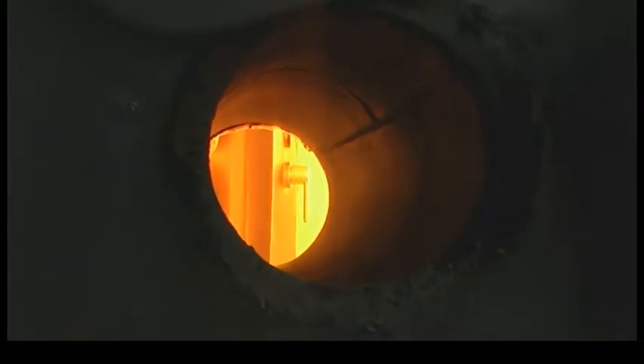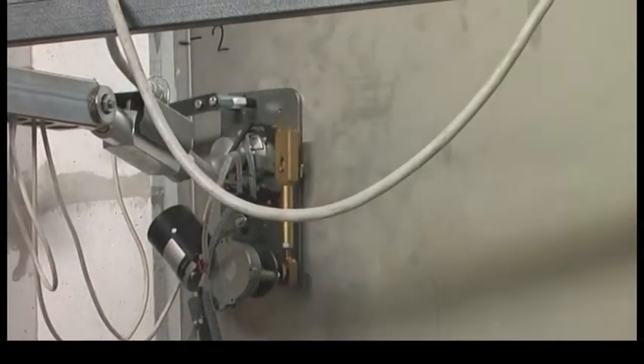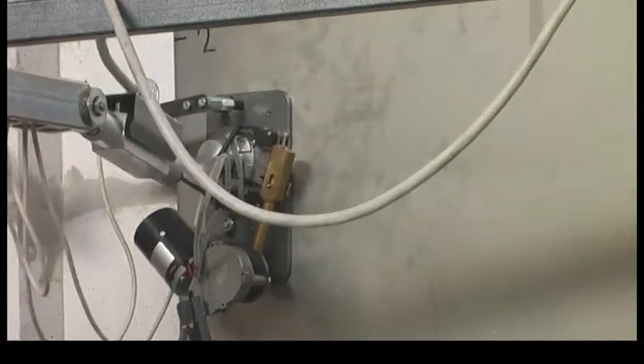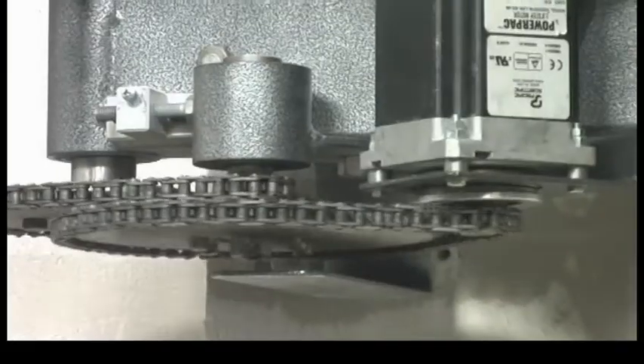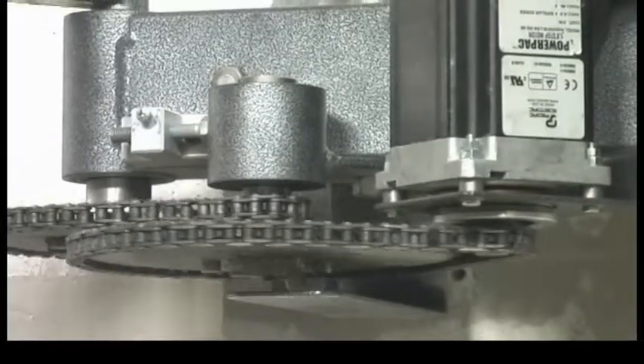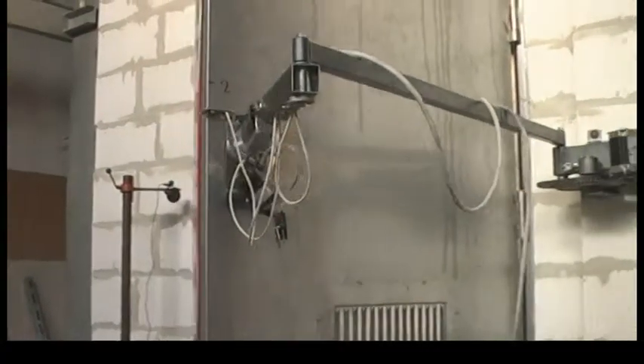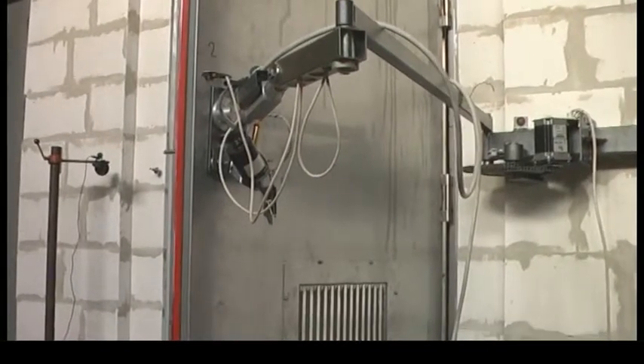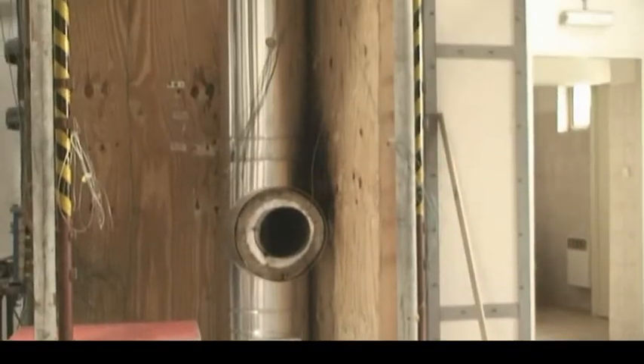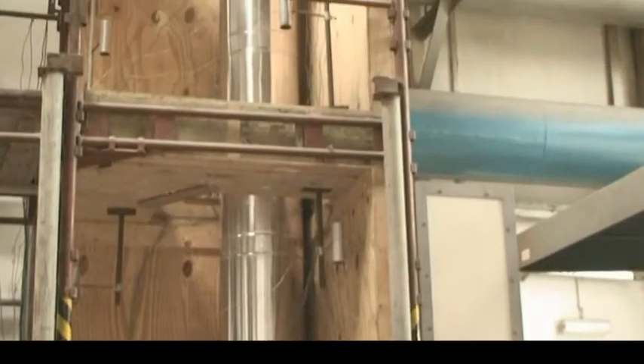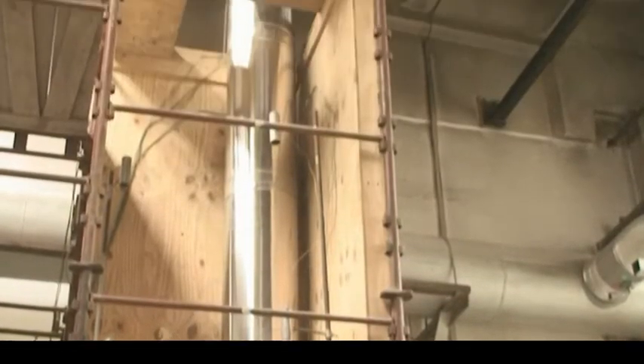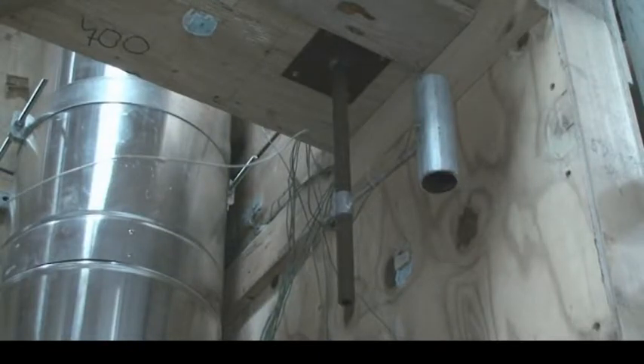Along with door assemblies, not only their fire resistance, but also their mechanical properties may be tested. Those include resistance to cyclic opening and closing, resistance to vertical loading, resistance to static torsion, resistance to impact of a soft and heavy body, resistance to hard body impact. For the initial type testing of chimneys and chimney systems, a hot gases generator is used. This helps to carry out the tests of heat stress due to the test temperature, according to the given temperature and pressure class, including tests of soot fire resistance.